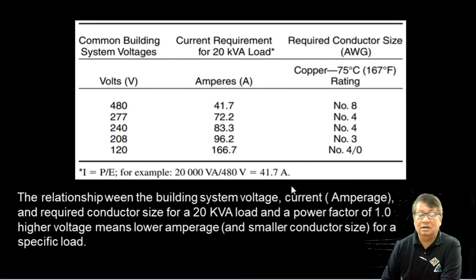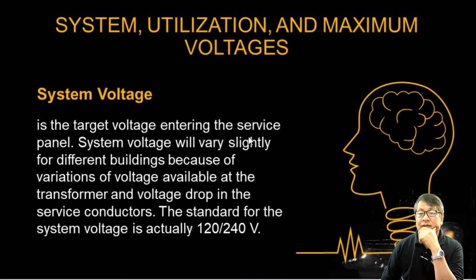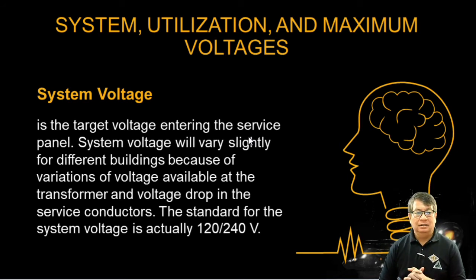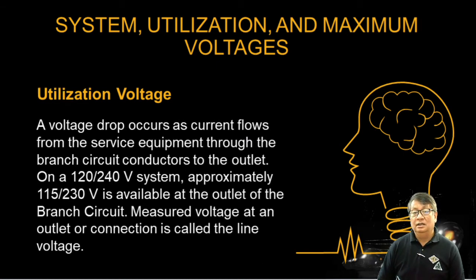This is also something we should know. The relationship between the building system voltage, current, and required conductor size for 20 kilovolt-amperes. Okay, so we have this minimum requirement. What is system voltage? It is the target voltage entering the service panel. System voltage will vary slightly for different buildings because of variations of voltage available at the transformer and voltage drop in the service conductors. The standard for the system voltage is 120 or 240 volts.